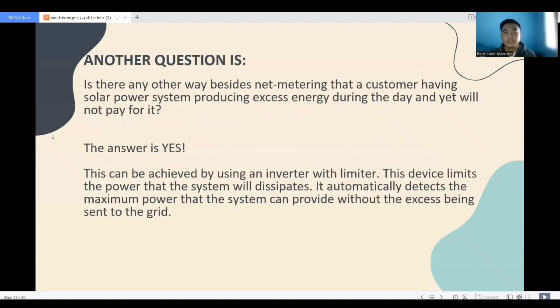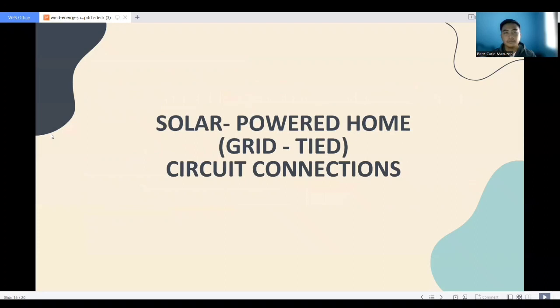Another question: is there any other way, besides net metering, for a customer having a solar power system producing excess energy during the day to not pay for it? The answer is yes. This can be achieved by using an inverter with a limiter. This device limits the power that the system will dissipate. It automatically detects the maximum power that the system can provide without the excess being sent to the grid.